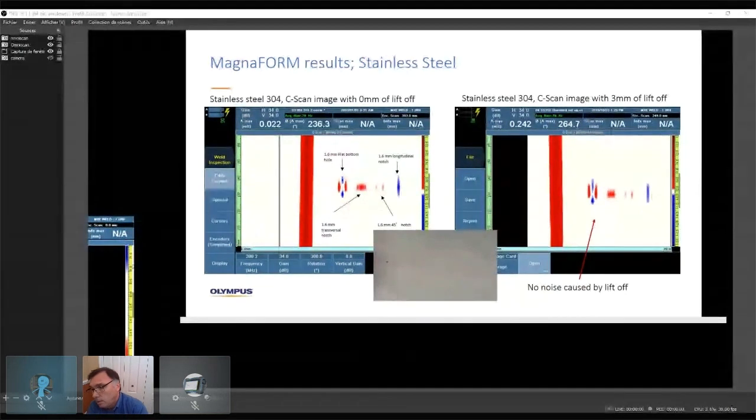PT outside, you have to apply your penetrant, and you have to respect the dwell time in the procedures, and then you have to wash. Imagine if you have to wash a corroded surface, because you can have stainless steel corroded in some cases, or if it's dirty, it's a big job, because penetrant is penetrant. So you have to wash and wash.